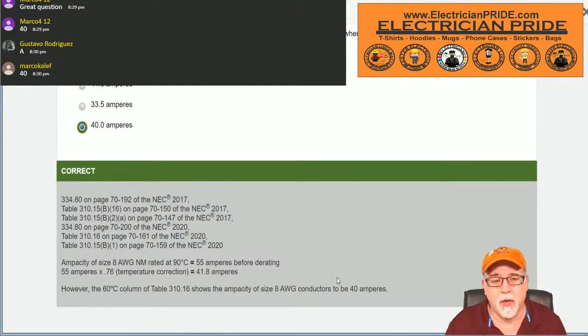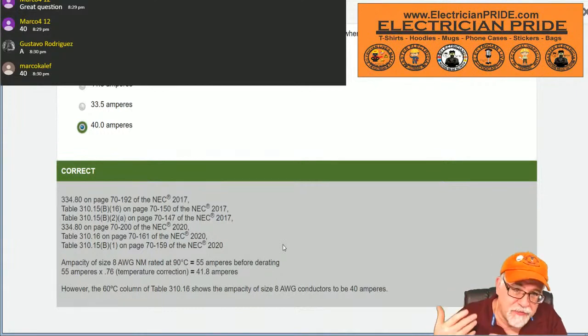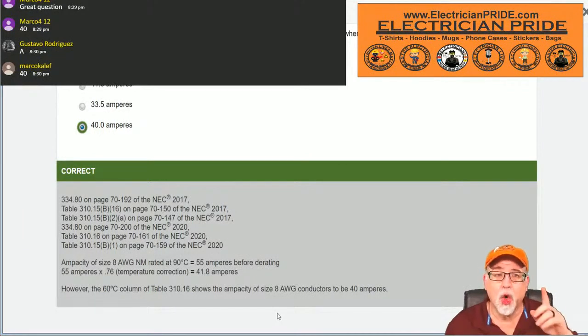Really, it is. Great question, and I tried to give you as many hints as I could. I don't want you to get that one wrong on an exam. Okay, this doesn't have to just apply to NM cable. This is a good rule when you're applying anything when it comes to adjustment and corrections based on the terminal limitations in 110.14(C), whether it's 100 amps or less using the 60 degree, over 100 amps using the 75, or if it's under 100 amps, but the conductors are rated 75 and the terminals are rated 75, then I get to use the values under the 75. Okay? Great. If you haven't watched my course on derating demystified, go watch it. It really covers all this information.